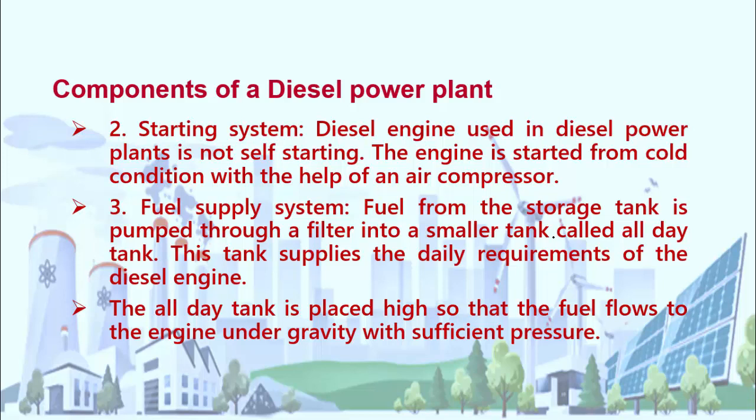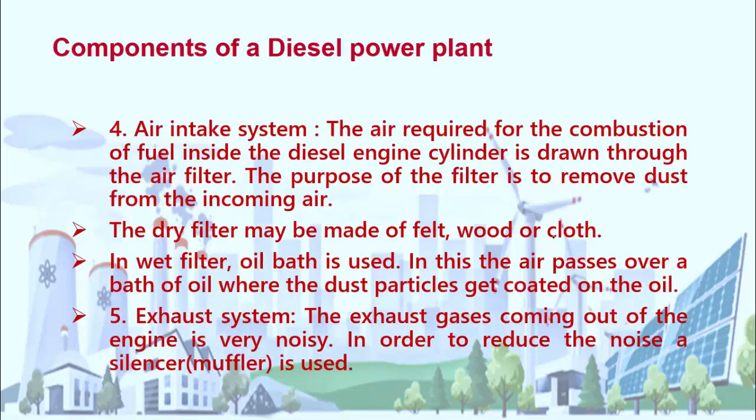The first component is the diesel engine. Already we have discussed that. The second component is the starting system. Diesel engines used in diesel power plants are not self-starting, right? The engine is started from the cold condition with the help of air compression. That is the starting air circuit we have seen, no? That is the starting system. And the third one is the fuel supply system. I told you the fuel supply system has a filter and a day storage tank, and all those things come under the fuel supply system, right?